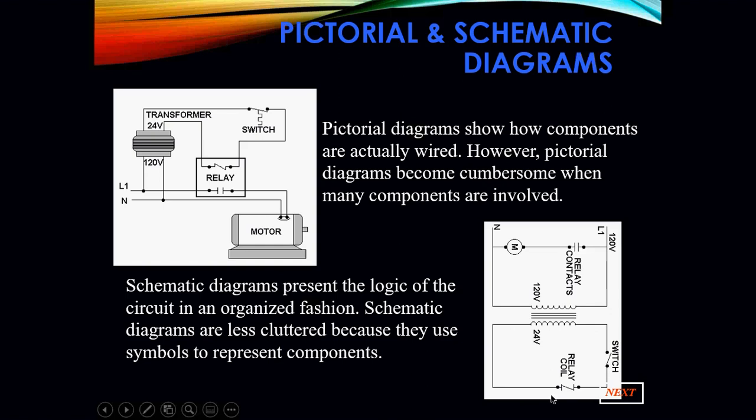Right here, big circle. That switch has to close first in order for the next line and for the next component in that line to operate. And in this case, it's a coil. Once that coil gets energized, everything happens on my 120 volt side. My contact will close, which will then energize my motor.